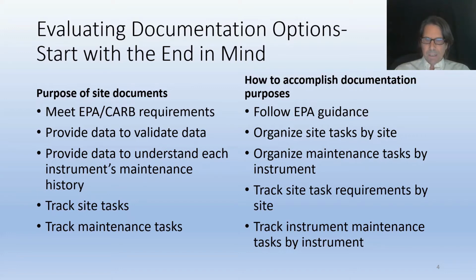But a second equally important purpose of our site documentation is to have a record of the history of performance and maintenance that's been performed on each instrument. And so the documentation systems really serve these two purposes.